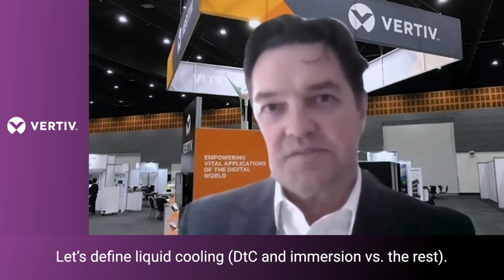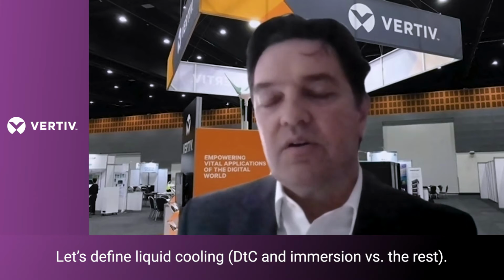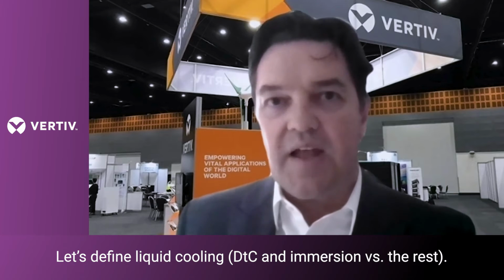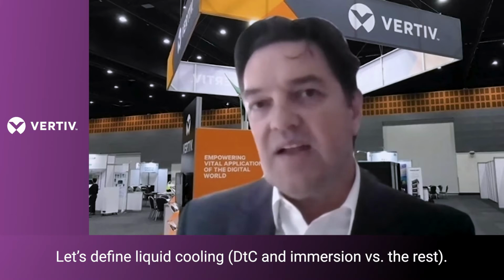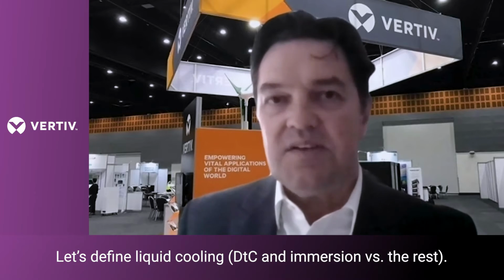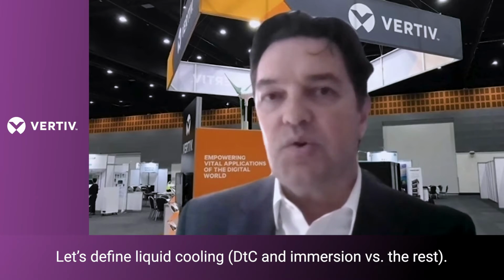The other type of liquid cooling uses dielectrics. These are fluids that are dielectric by nature, which means they do not conduct electricity and are insulators, so they can come into direct contact with the electronic components. They are used in a technology called immersion, where the electronic devices are immersed inside tanks, chassis, or containers that hold not only the liquid but also the communication or server devices.